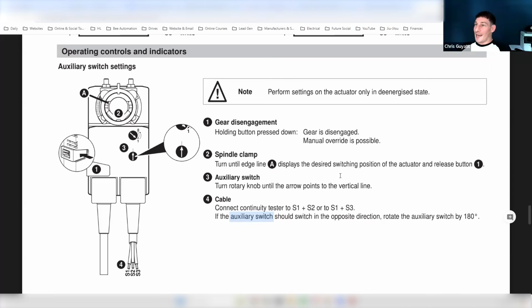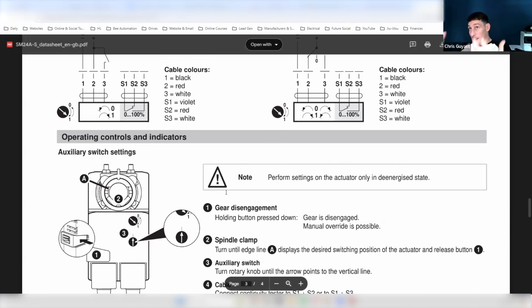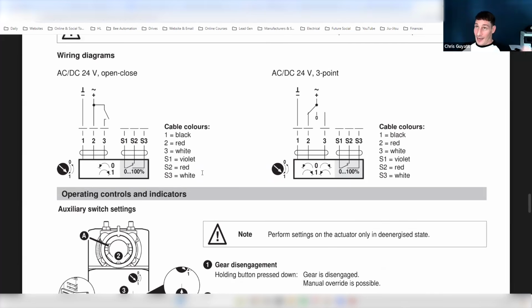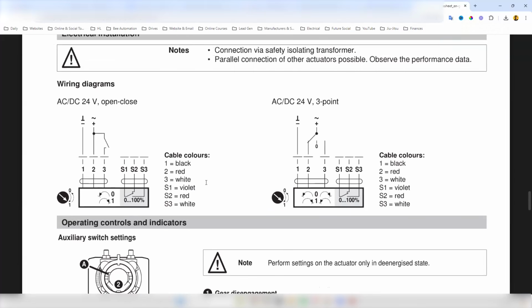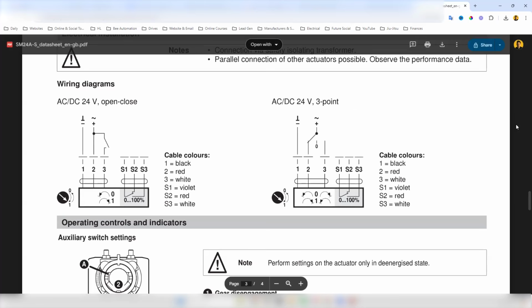What an auxiliary contact is, it's basically a switch. So Marlon, it's actually an output. Let me explain what this is doing on this actuator, because ultimately a valve - sorry Chris, just looking at the example you've given, I think it makes sense. With a standard heating system, we send a signal out typically to our 2-point valve actuator. That will rotate around, and that then brings into play, basically connects to - it's like a switch that tells us what a given situation is. Right, so when that contact closes, we know there's a call for heat, and that switch essentially tells us yes, we have that call for heat.